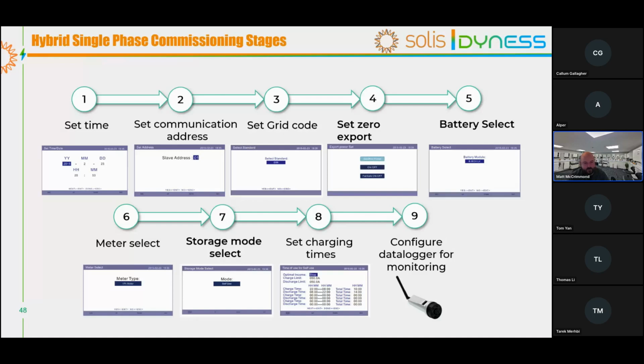Setting the communication address. This is always set at 01 by default. We have had customers accidentally change it. If you do have an issue and you set the slave address to 02, for example, you can go in and change it at a later date. However, what you would see is you would see an issue with your data logger, because your data logger is always looking to try and connect to the 01 inverter.